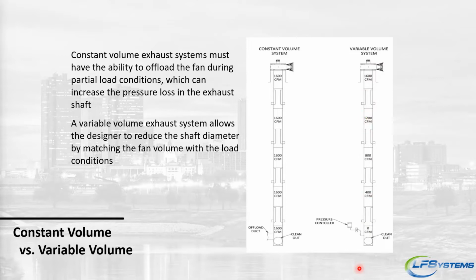So when it's running at peak capacity, it may be running at 80 to 90%, but during the middle of the night, when no one's using the dryers, no one's using their bathrooms, that fan is going to ramp down to its lowest speed, typically 10 to 15% of its capacity, and just sit there at minimum speed. So we're maintaining that code requirement of constant flow, but we're not having to deal with constant speed. We're not wasting all of that air being pulled up through that shaft. Now we won't even need that offload duct. It's just getting a little bit of air from each space to maintain that minimum CFM.